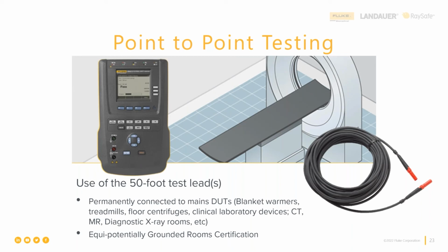So how do you do that? I mean, you've got a safety analyzer, you've got about a 3-foot test lead or 2. In this case, we're going to use point-to-point testing. So how are we going to make that happen? Well, the way we're going to make that happen is to use longer test leads.